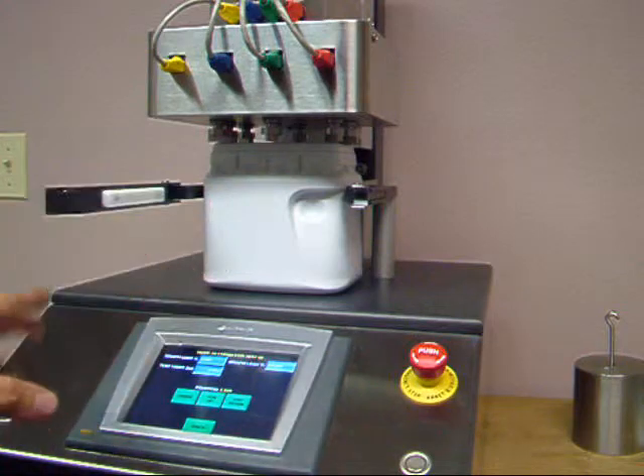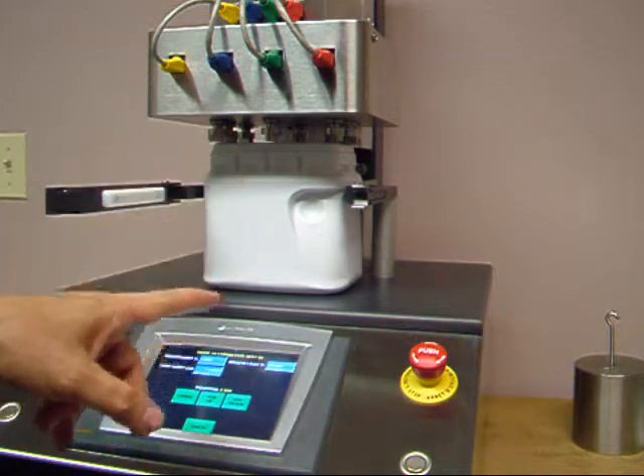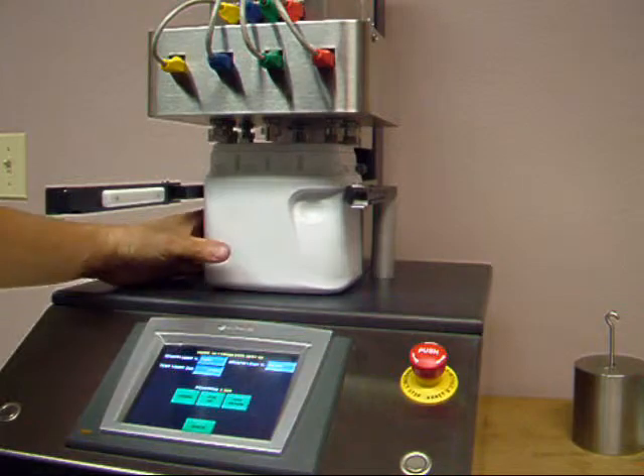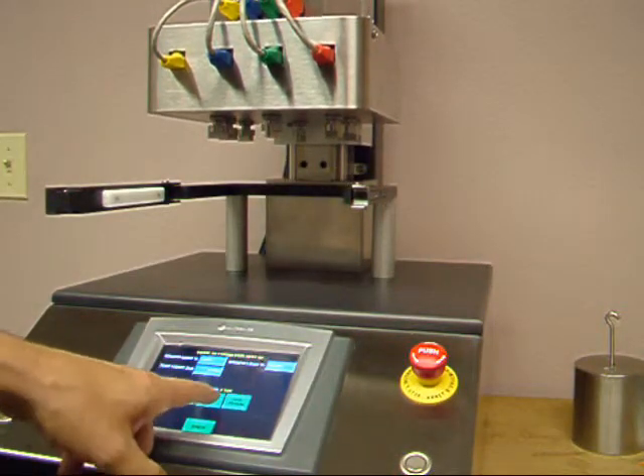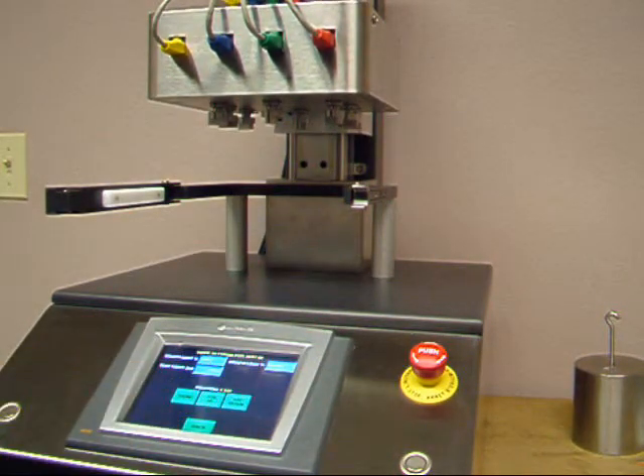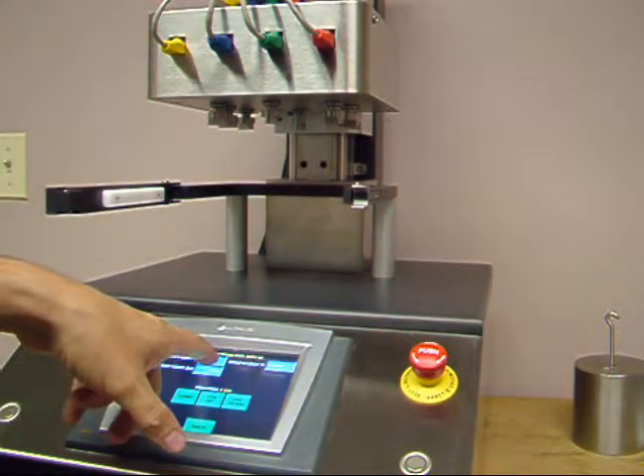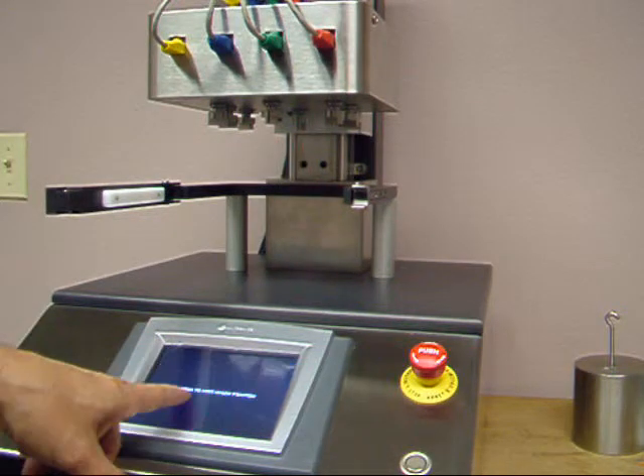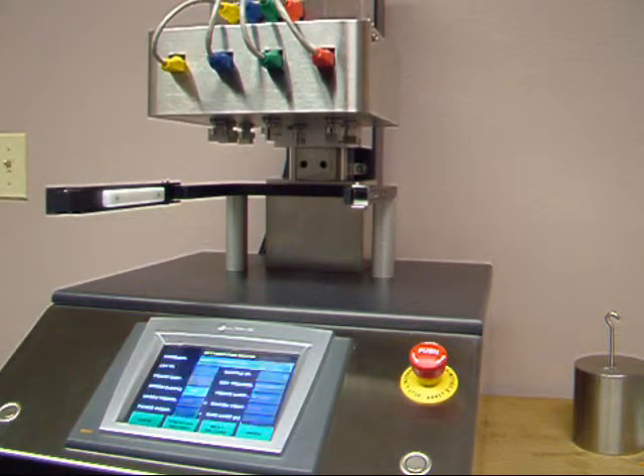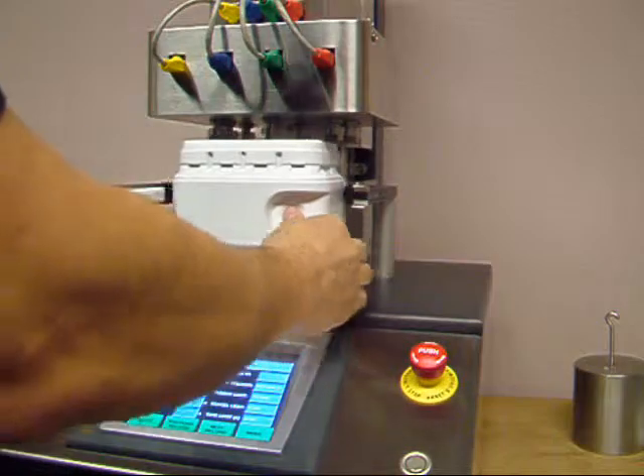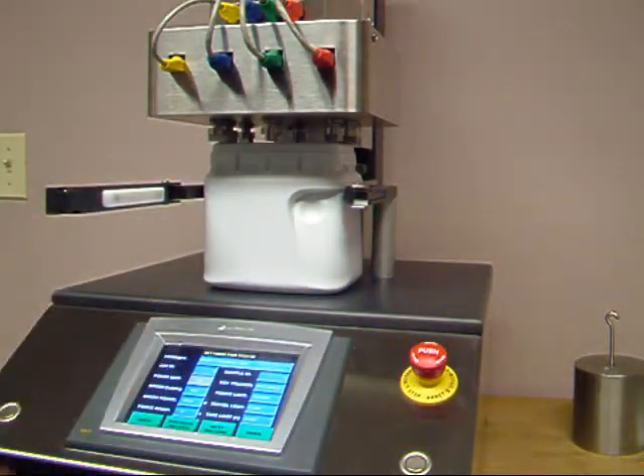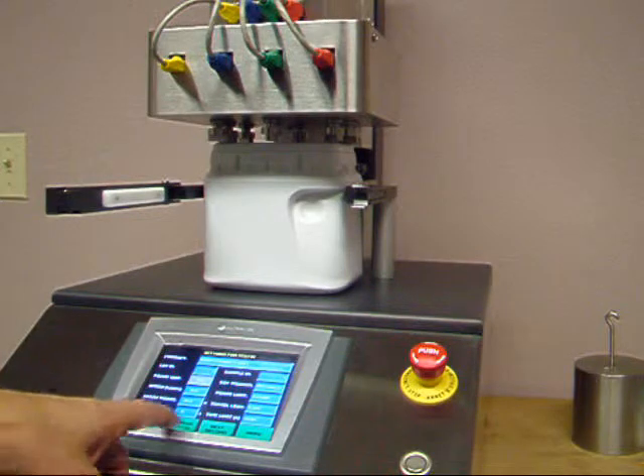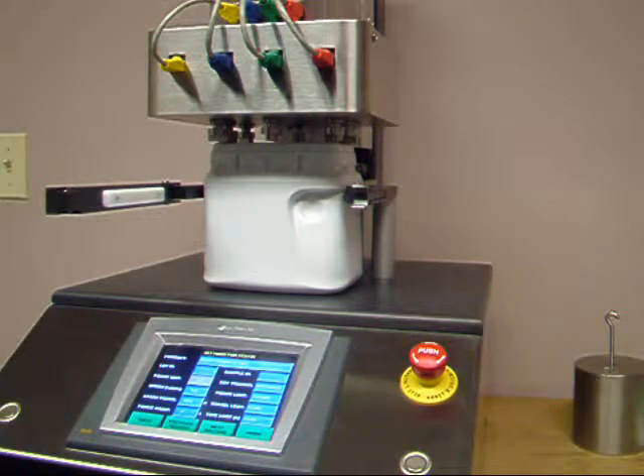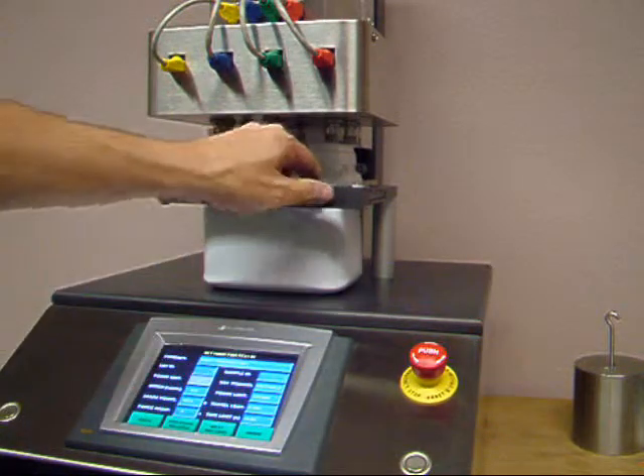The home position for this bottle is already determined. If for some reason you have to change it, you can manually jog up and down to the right position where you would like to start from, and enter that number in the test home field, and then you can press the home key and that's going to bring it to the home position. And that home position is associated with this test recipe, so if you change to a different test recipe, the home position will automatically follow. But I'll show you that.